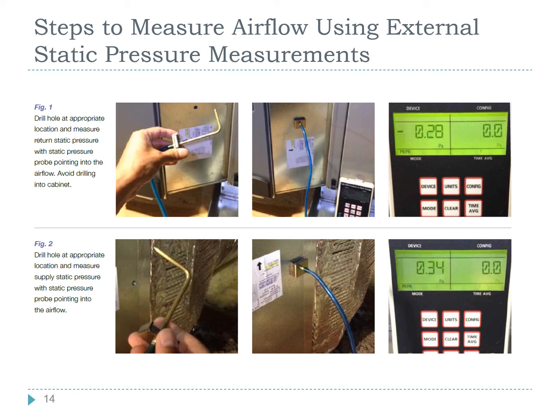Here are the steps to measuring airflow using external static pressure measurements. In Figure 1, you can see you need to drill a hole in the appropriate location to measure the return static pressure with the static pressure probe pointing in the direction of airflow, and avoid drilling into the cabinet if at all possible. You're going to want to measure that on the furnace side of the filter. Then in Figure 2, you can see drill a hole in the appropriate location and measure the supply static pressure, and also have that probe pointing into the direction of airflow.